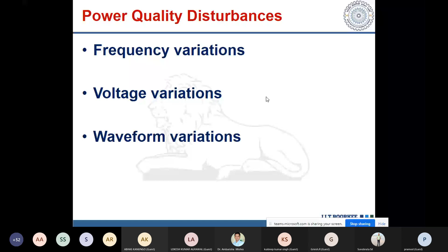Voltage variation may be long duration, you can have short duration, you can have voltage imbalance, you can have voltage fluctuation, you can have transient. As far as the first four are concerned, in all these cases, the voltage is sinusoidal, although it may be different than the rated one. And there are different reasons to have over voltage, under voltage, or sustained interruption, or you can have sag, swell, voltage imbalance, voltage fluctuation. In all these cases, the voltage waveform remains sinusoidal.